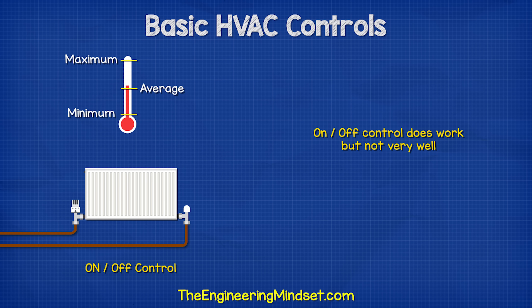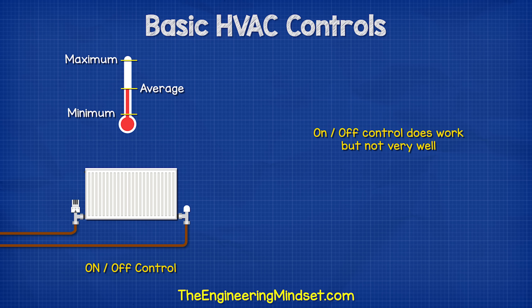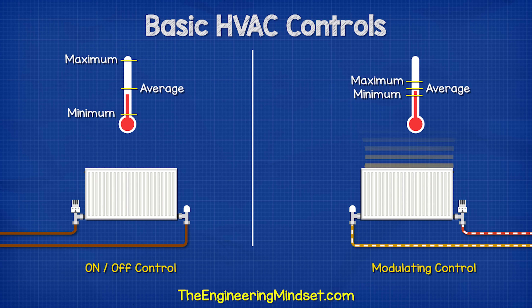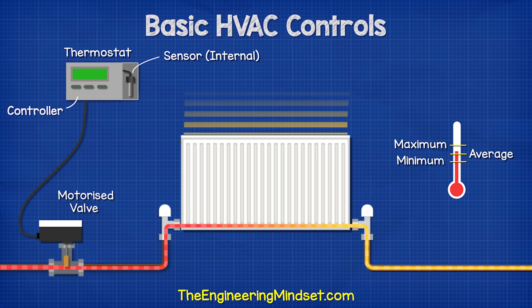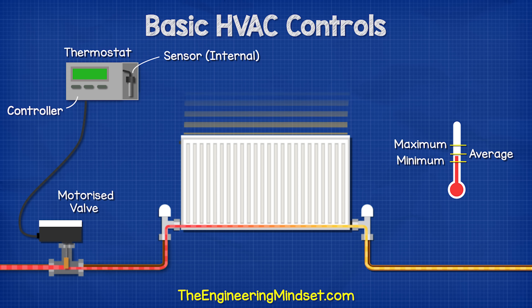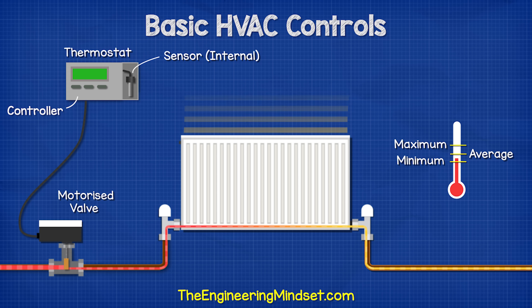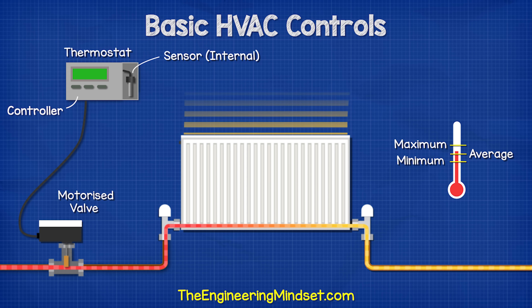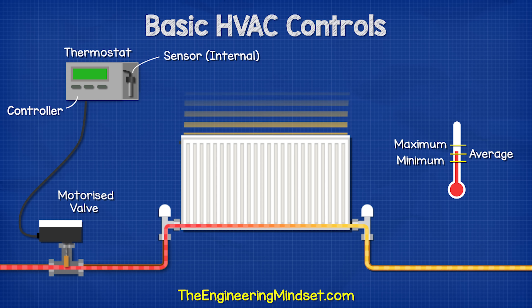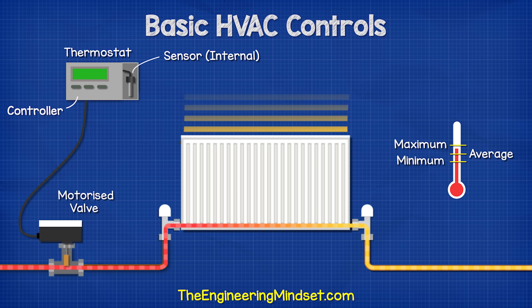Turning systems or components on and off to regulate the room temperature does work, but not very well. Instead, we can modulate the thermal output by increasing and decreasing the temperature to match the actual load. For example, in this simple heating system, we have a thermostat in the room to measure the temperature, and then a controller will compare this to the desired set point temperature and decide if the room is too hot, too cold, or just right. If it is too cold or too hot, the controller alters the position of the motorized valve to increase or decrease the amount of hot water entering the radiator.